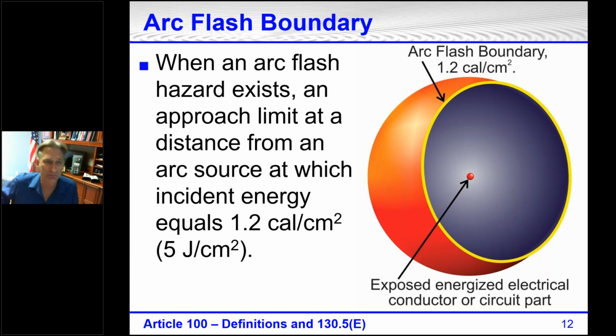Here's the definition of the arc flash boundary. It says, and this is in Article 100, and also it's covered again in 130.5E: when an arc flash hazard exists, an approach limit at a distance from the arc source at which incident energy equals 1.2 calories per square centimeter or 5 joules per square centimeter.